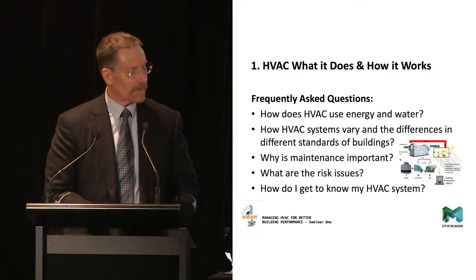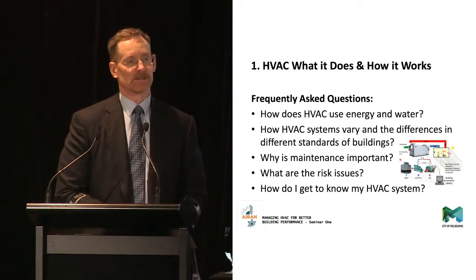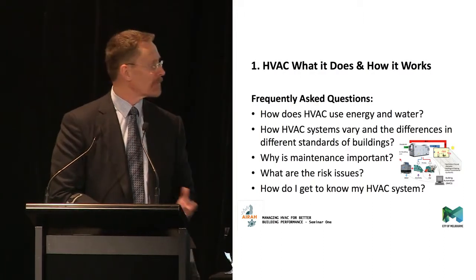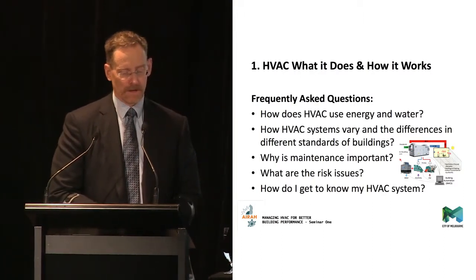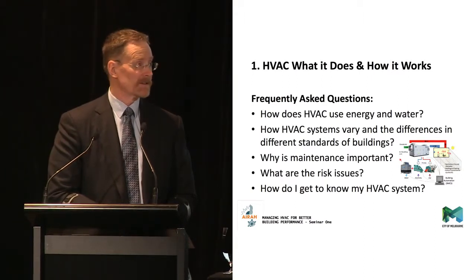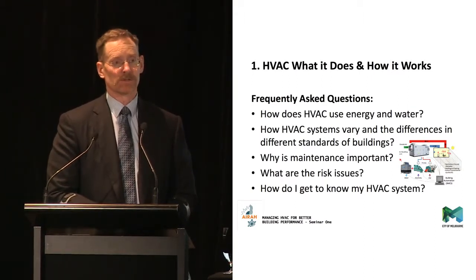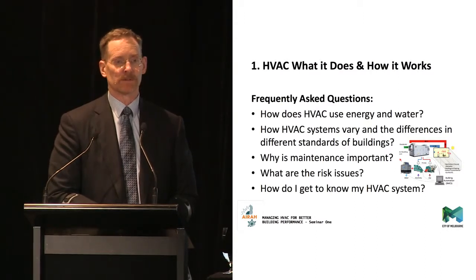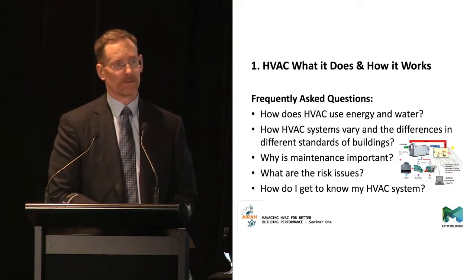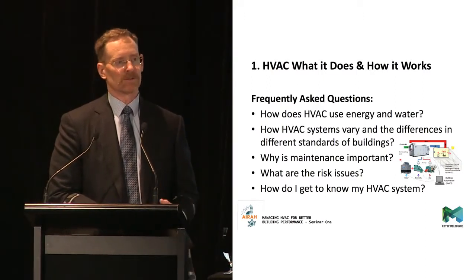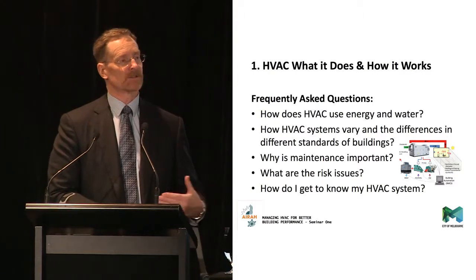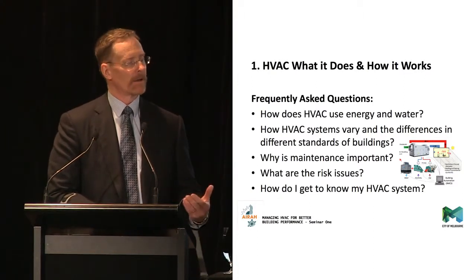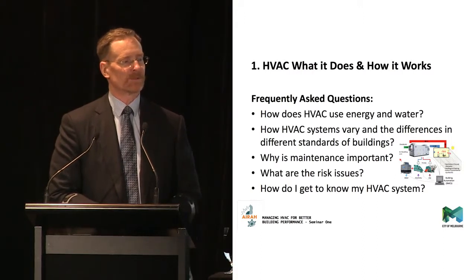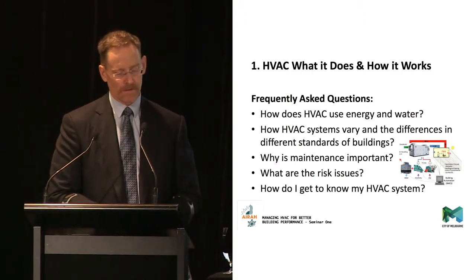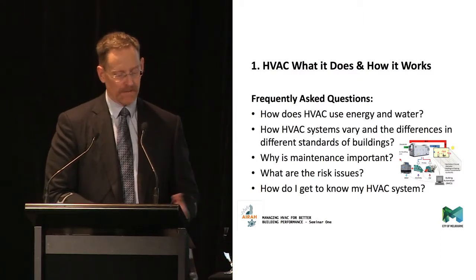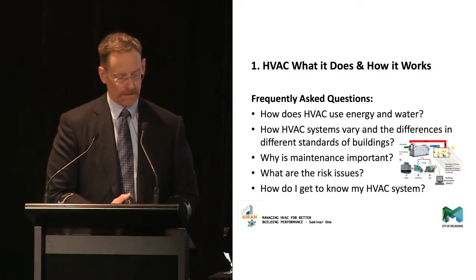So how do HVAC systems vary? Obviously they don't all look like this - this is very much a generalisation, there are 101 different variations on the process. One important variation we've seen in the last 5 or 10 years is chilled services, chilled beams. Council House 2, mentioned before, has chilled beams - these are cooling or heating surfaces in a space that radiate heat or cooling, but are cooled by chilled water and heated by heating hot water, so the componentry is the same. You still have chillers, boilers, air handling units, and an air distribution system.